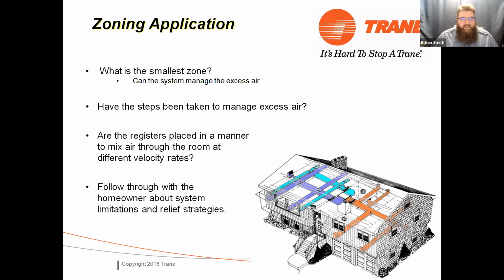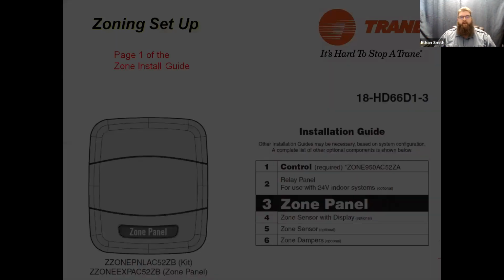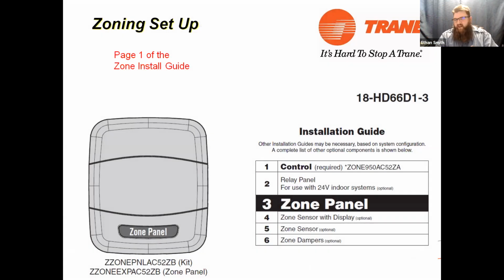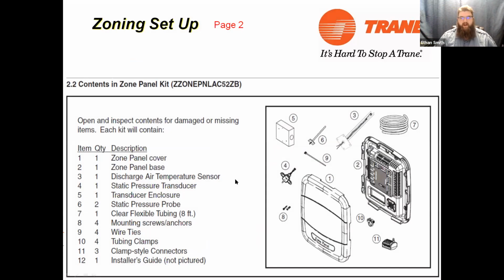But we've got to talk about realistic expectations, understand how the zoning system works. It's not made to give you dramatic temperature shifts through the house. It's made to make each area as comfortable as possible. Okay. So that being said, guys, here's a look at the Trane and American Standard zoning systems. This is straight out of the installation guide, page 1. So this is the zone panel. It is not made by Honeywell, contrary to popular belief. This is a Trane American Standard product through and through.